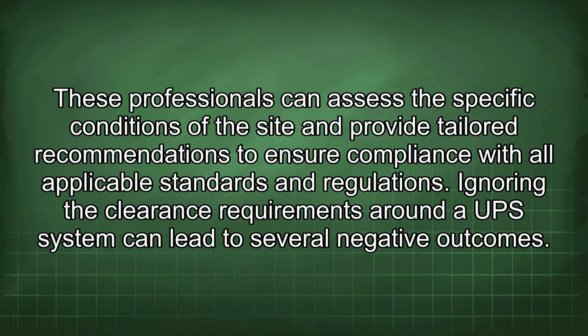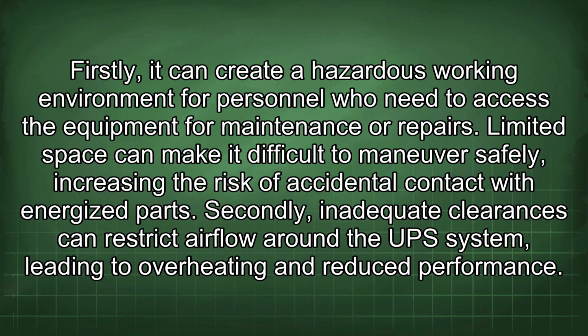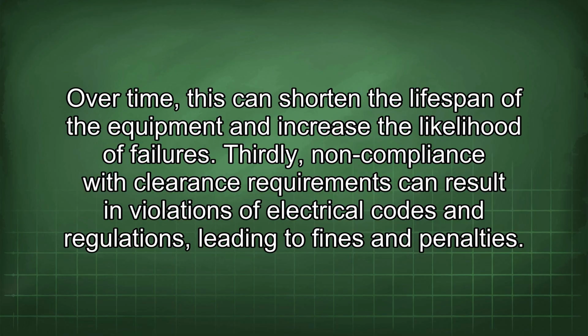Ignoring the clearance requirements around a UPS system can lead to several negative outcomes. Firstly, it can create a hazardous working environment for personnel who need to access the equipment for maintenance or repairs. Limited space can make it difficult to maneuver safely, increasing the risk of accidental contact with energized parts. Secondly, inadequate clearances can restrict airflow around the UPS system, leading to overheating and reduced performance. Over time, this can shorten the lifespan of the equipment and increase the likelihood of failures. Thirdly, non-compliance with clearance requirements can result in violations of electrical codes and regulations, leading to fines and penalties.